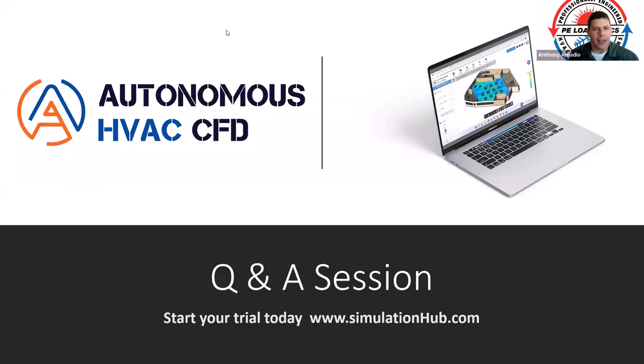Before CFD, that was kind of the way we would select or locate a diffuser the best we could, although it was very limited information. Don't get me wrong, it could still be used as a guide, but there are so many more scenarios where you fall outside the box of the ADPI. If the question is how do I use the ADPI, there's an example in Chapter 58 applications, but you just need to know what diffuser you're using, what type, and what the CFM is.